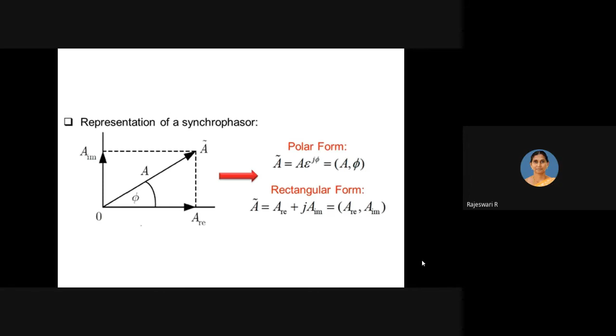So what is PMU, phasor measurement unit? We need to measure this phasor at various points of the network, and this is performed by an instrument called a phasor measurement unit, the instrument which measures phasor. It requires the GPS signal to give time reference, so it should have GPS accessibility.